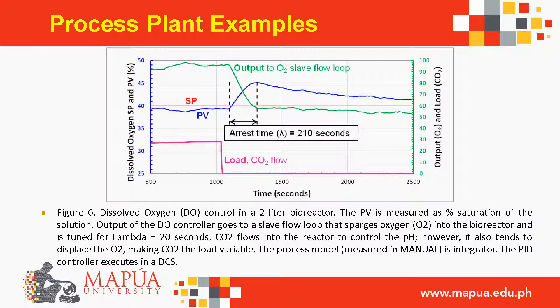Dissolved oxygen control in a two-liter bioreactor: the PV is measured as percent saturation of the solution. Output of the DO controller goes to a slave flow loop that sparges oxygen into the bioreactor, tuned for lambda = 20 seconds. CO2 flows into the reactor to control pH but also displaces O2, making CO2 the load variable. The process model is integrator; the PID executes in a DCS.